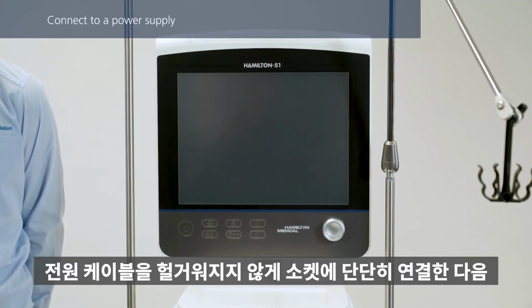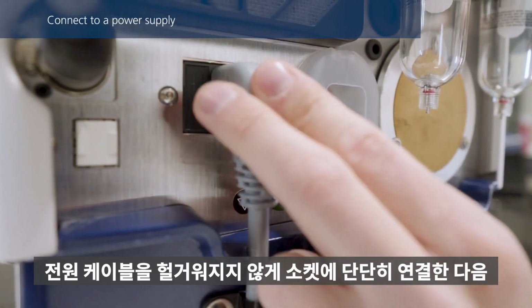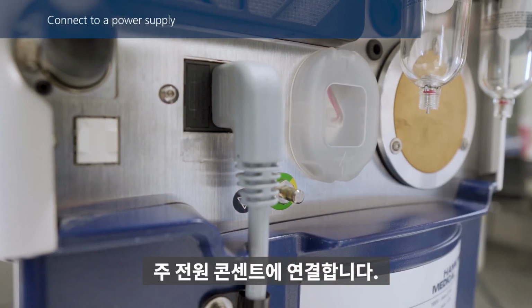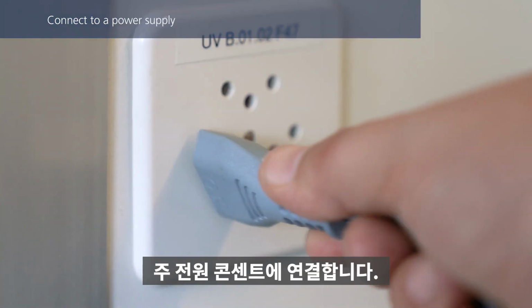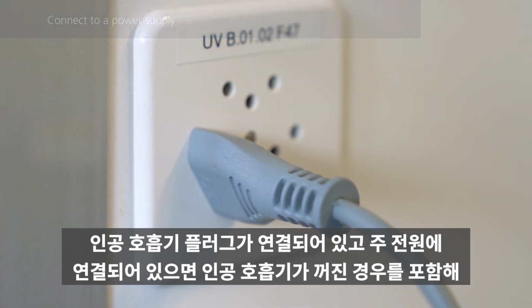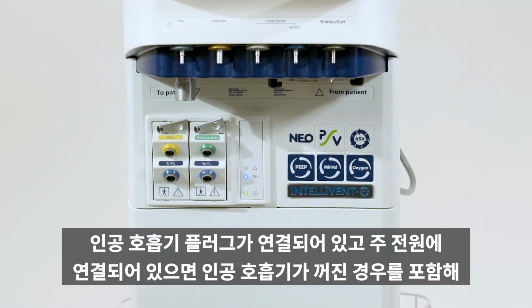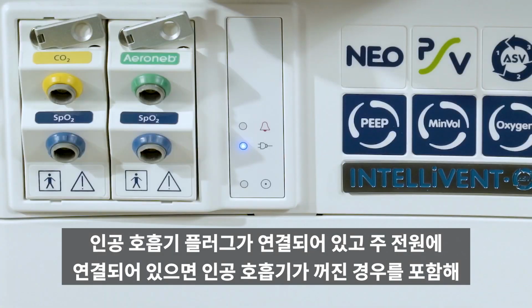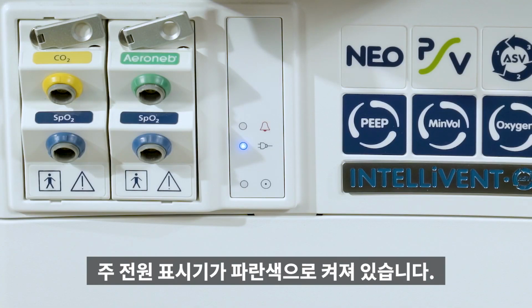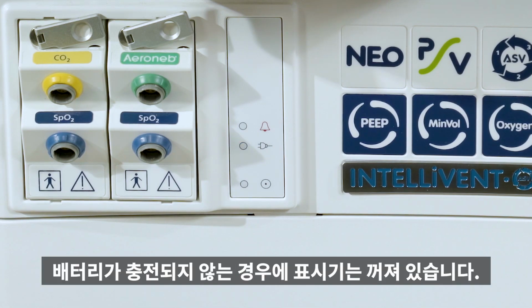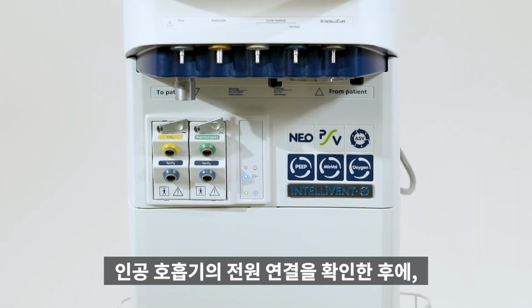Make sure the power cable is firmly connected in the socket to prevent accidental disconnection, and then connect it to the primary power outlet. The primary power indicator is solid blue when the ventilator is plugged in and connected to primary power, even when the ventilator is turned off. If the battery is not charging for whatever reason, the indicator will remain dark. Make sure the ventilator is connected to a power source prior to starting ventilation.